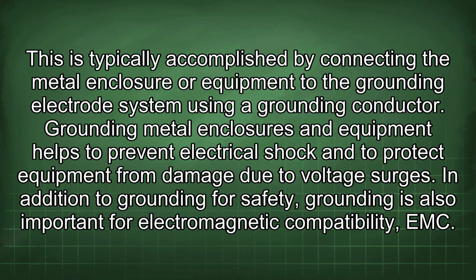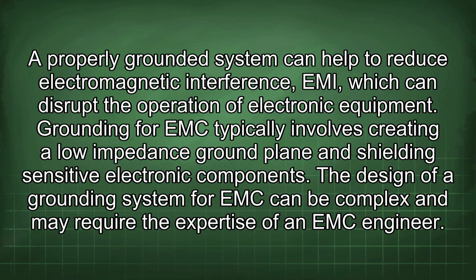In addition to grounding for safety, grounding is also important for electromagnetic compatibility (EMC). A properly grounded system can help to reduce electromagnetic interference (EMI), which can disrupt the operation of electronic equipment. Grounding for EMC typically involves creating a low-impedance ground plane and shielding sensitive electronic components. The design of a grounding system for EMC can be complex and may require the expertise of an EMC engineer.